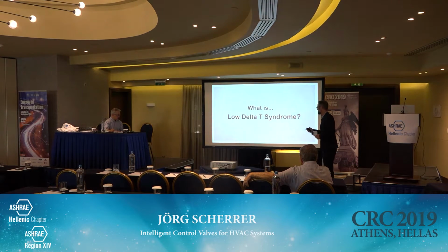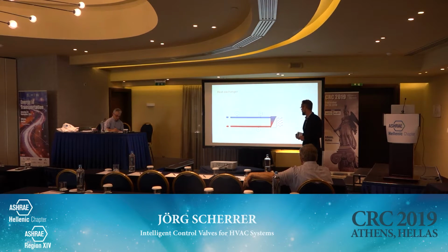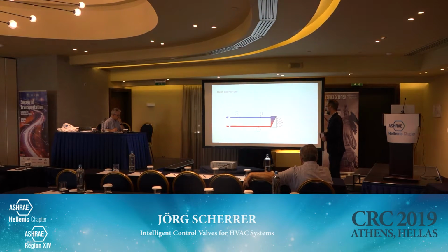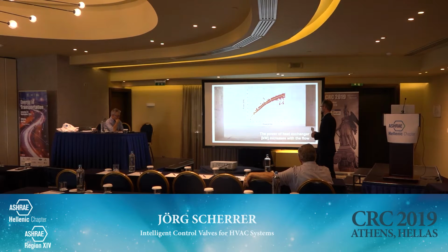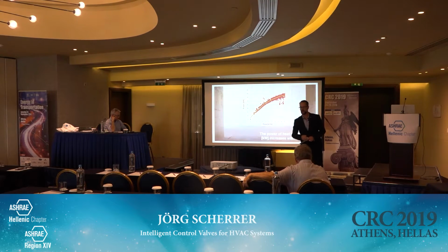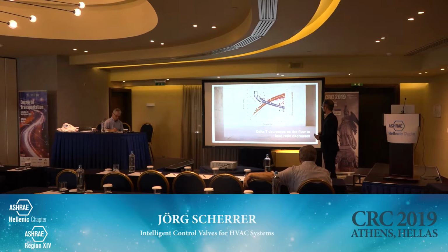Low delta T syndrome: if you have a heat exchanger with a supply and a return in a heating application, we have a supply temperature and a return temperature. What we call the low delta T syndrome, I'm sure you have already heard this name, is a mismatch between supply and return temperature. So I have too much water for the power output and energy consumption at the heat exchanger. Here you see the characteristic of a heat exchanger. The more flow I have, the more power I get on this heat exchanger. And the delta T curve looks like this: with more flow, I have a smaller delta T, a smaller differential temperature between supply and return.